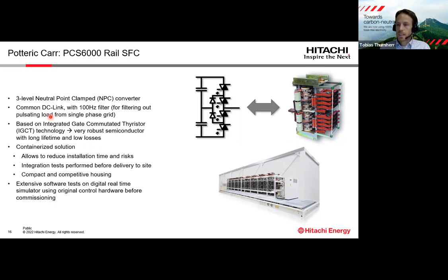Extensive software tests have been done on a digital real-time simulator before commissioning. So the original control hardware is interfaced with a computer that is calculating in real time the behavior of the power electronics and of the grid. And this allows us to do fast and very accurate testing of the software before going to site.